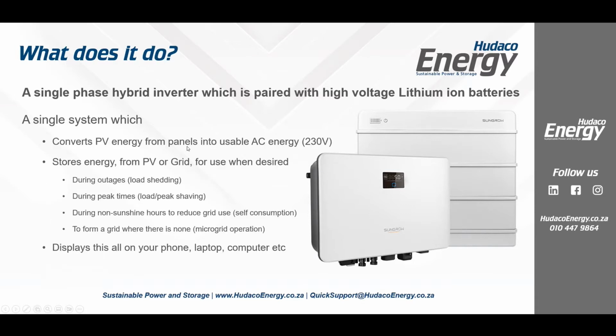What does it do? Okay, so it's an incredibly flexible system. You'll see when I talk about the architecture in just a moment. So it's one system which, just like everybody else, converts PV energy from panels into usable energy. It's single phase, so 230 volts is the standard. It also stores energy, so it's a full storage system, either from PV or from grid, for really 4 key things. Number 1, during load shedding, which we know in South Africa is really critical.